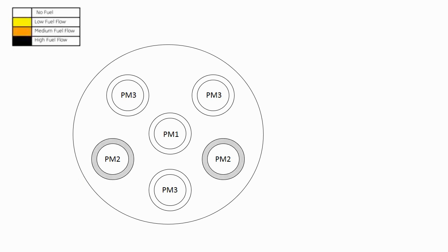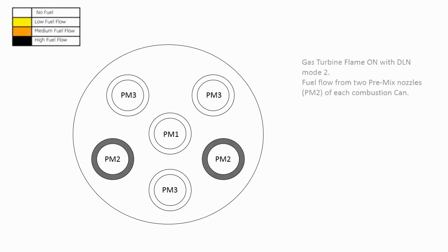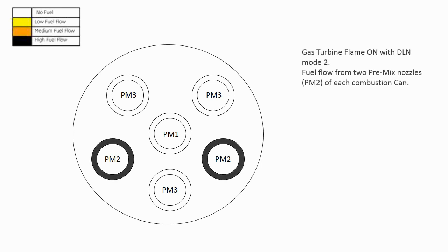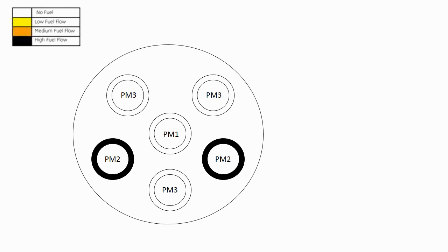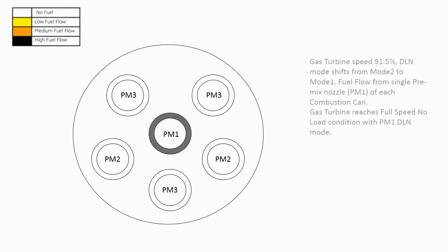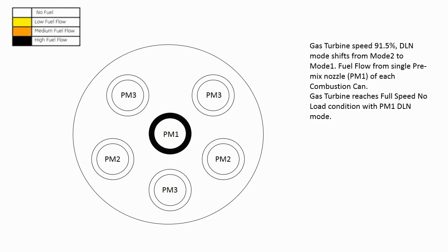7FA gas turbine flame-on with DLN mode 2. Fuel flows from two premix nozzles PM2 of each combustion can. When 7FA gas turbine speed reaches 91.5%, DLN mode shifts from mode 2 to mode 1. Fuel flows from single premix nozzle PM1 of each combustion can.